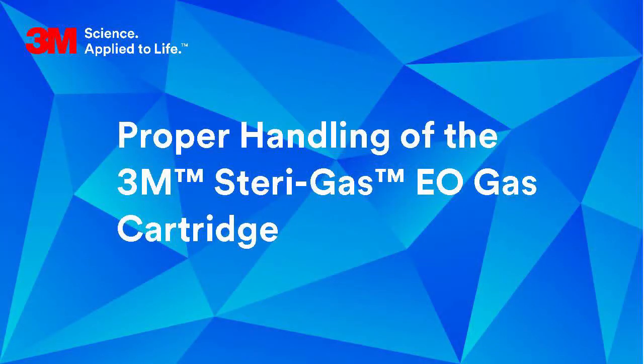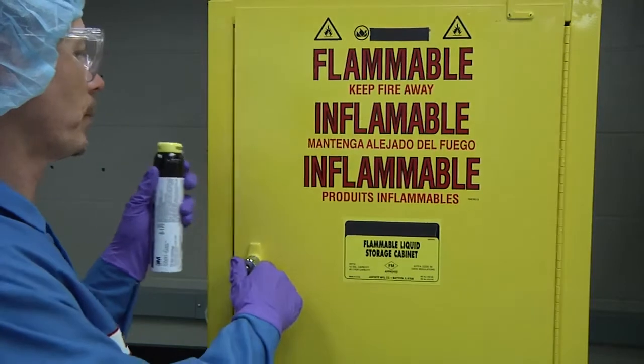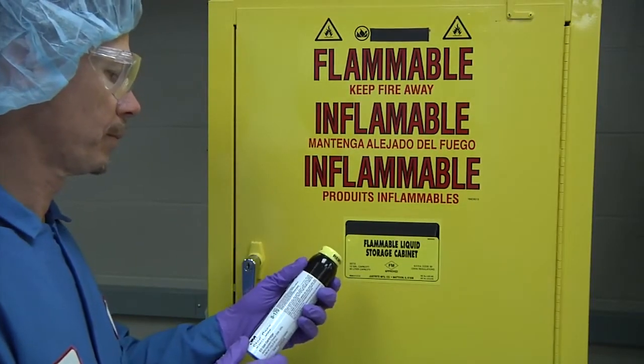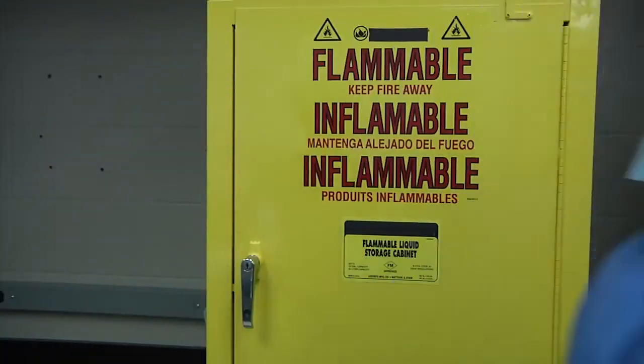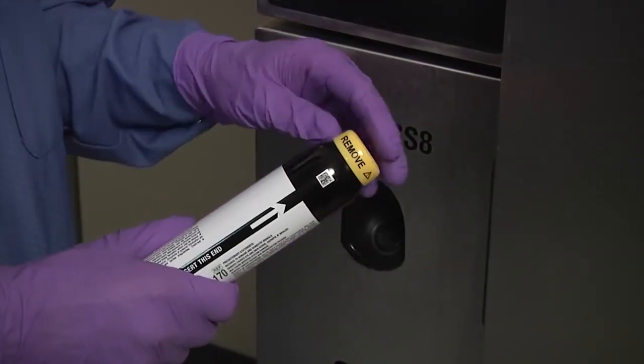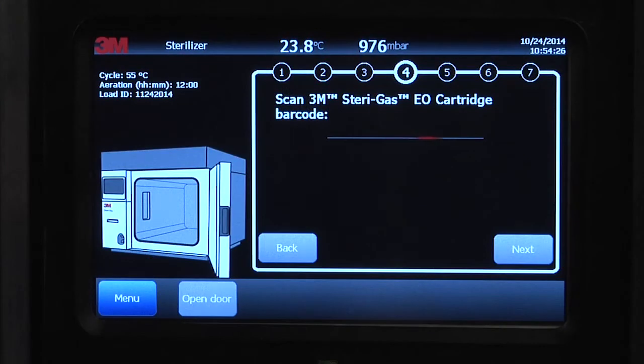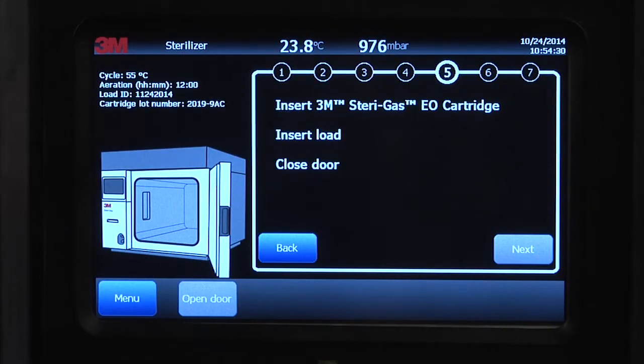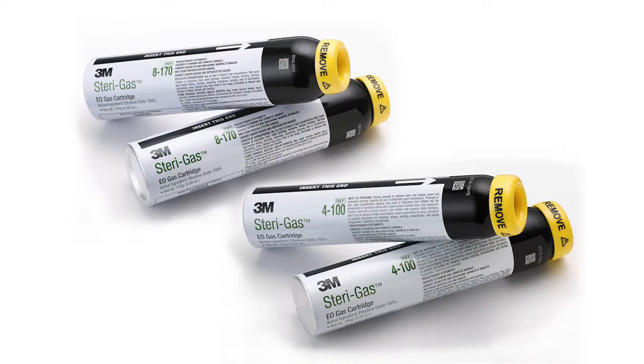Access a 3M Sterigas EO gas cartridge from the designated location per your facility's policies. Remove the protective yellow cap from the cartridge and proceed to Step 4. Step 4. Scan the 3M Sterigas EO gas cartridge barcode to ensure you are using a 3M Sterigas EO gas cartridge, the correct cartridge for the GS series sterilizer model, and a cartridge that is not expired or that has not previously been used.